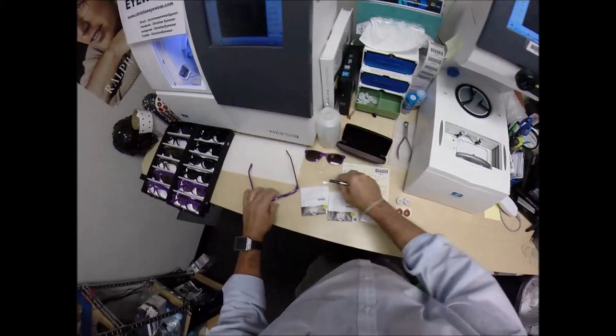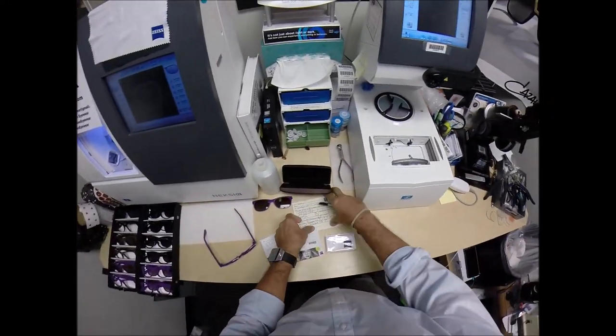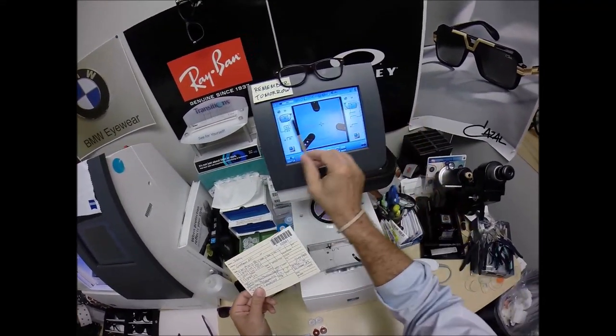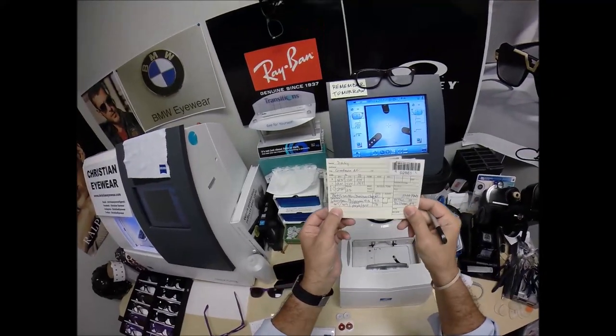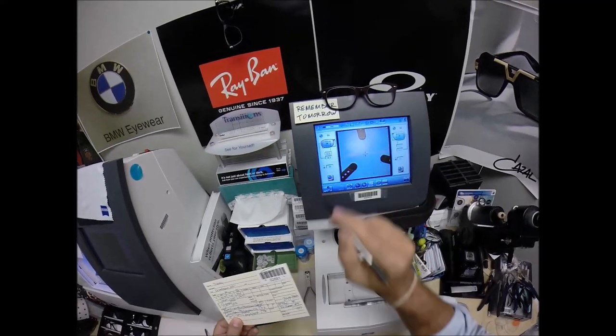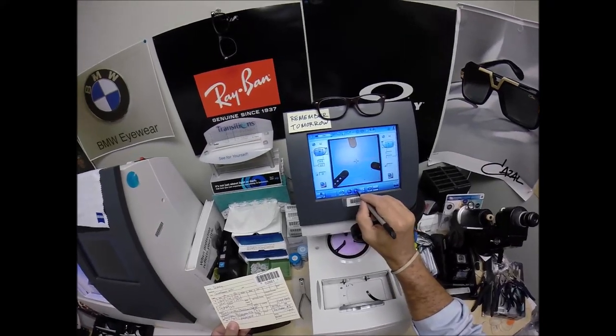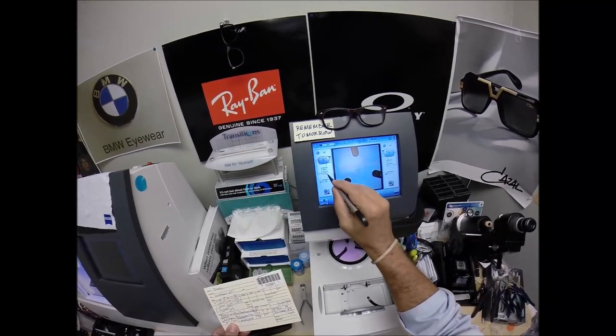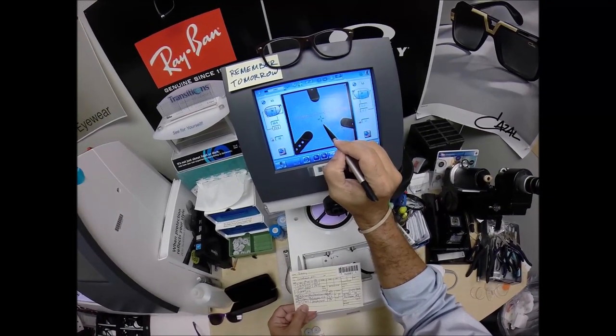Now that is the shape of the lens we'll be cutting. It's going to ask me to enter the coordinates — just like the crosshairs of a scope, I measure vertically and horizontally. The horizontal measurement, known as the pupillary distance or PD, is 30.5. The computer starts at 32.5, so I'm going to tap the minus button a few times until we get to 30.5. Then I raise the optical center height up to 23. This blue cross is the geometric center of the frame; the orange crosshairs sit directly in front of your pupil.